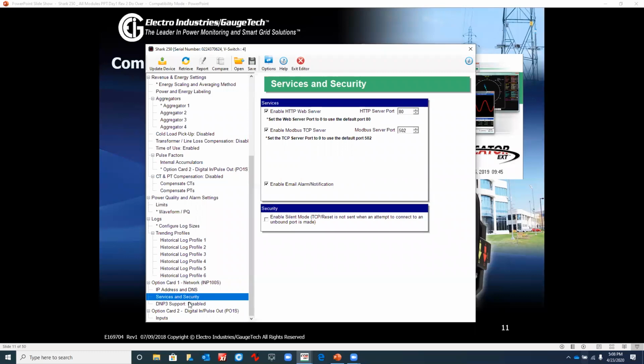And in this area, we talk about enabling the web server. The meter comes with a built-in web server, and so you can enable that so you can use any browser. In this case, port 80 is chosen. A lot of the companies might block port 80, so this gives you the ability to change that browser port number to anything other than port 80. So you have that choice.